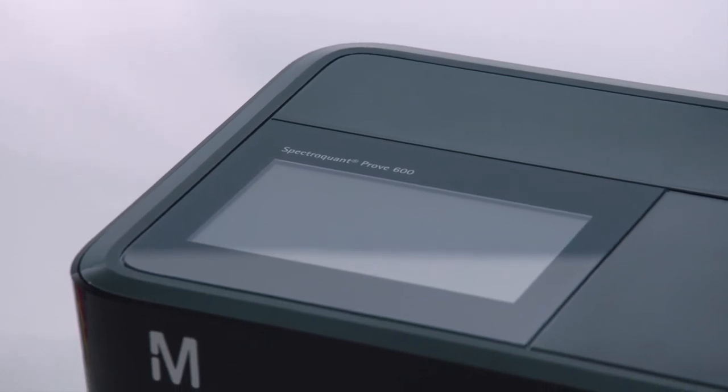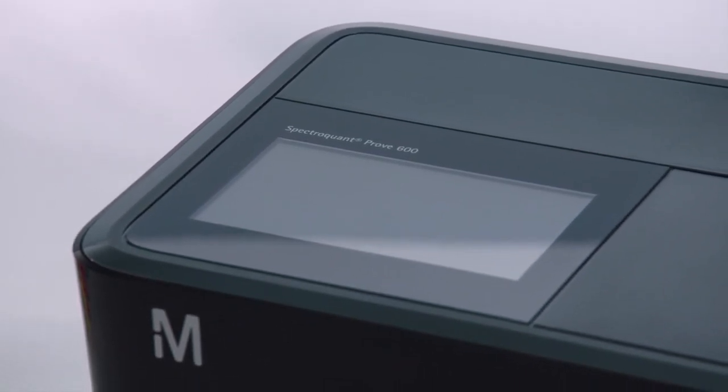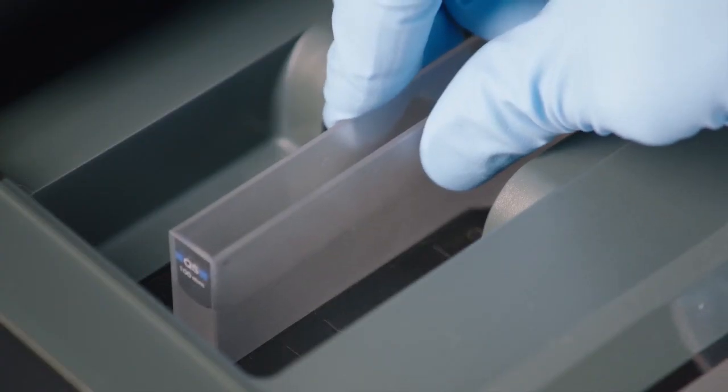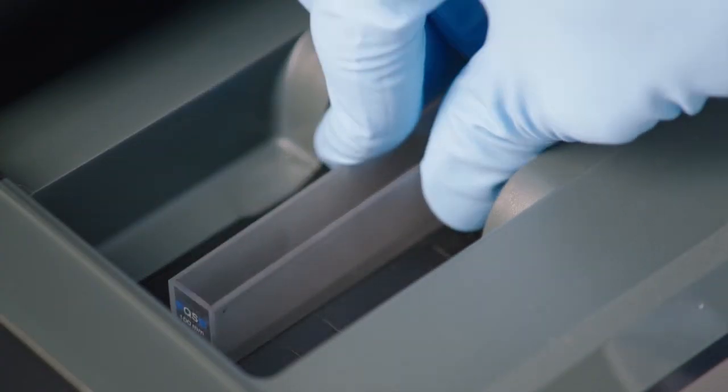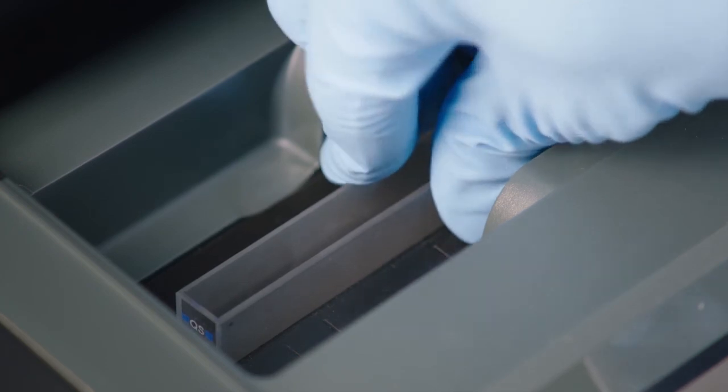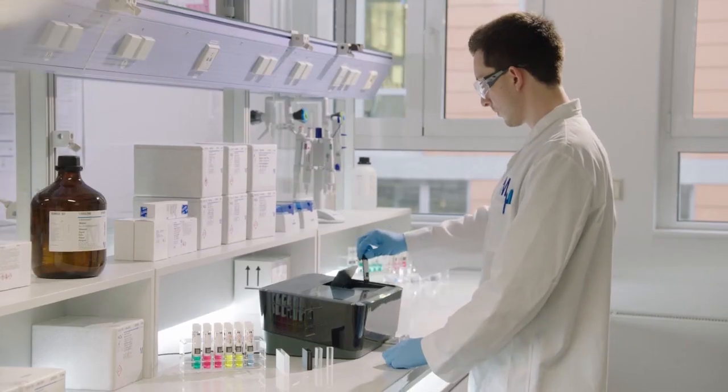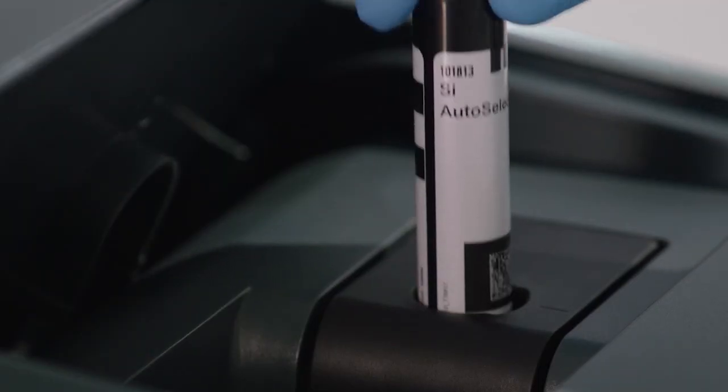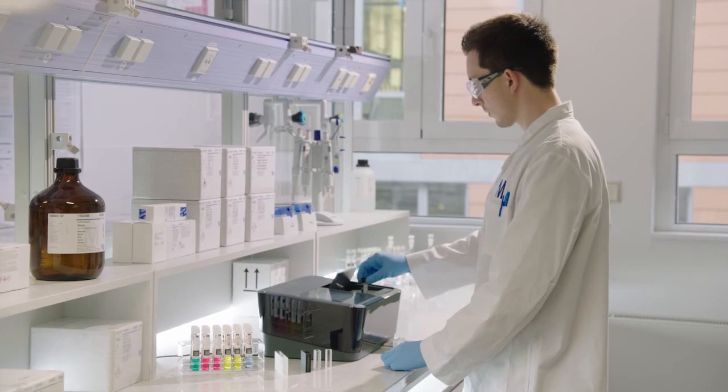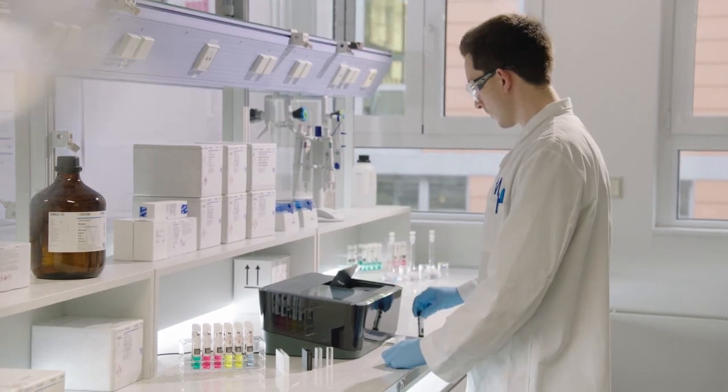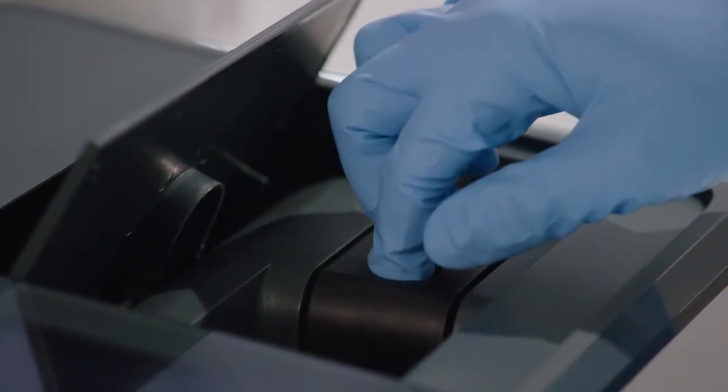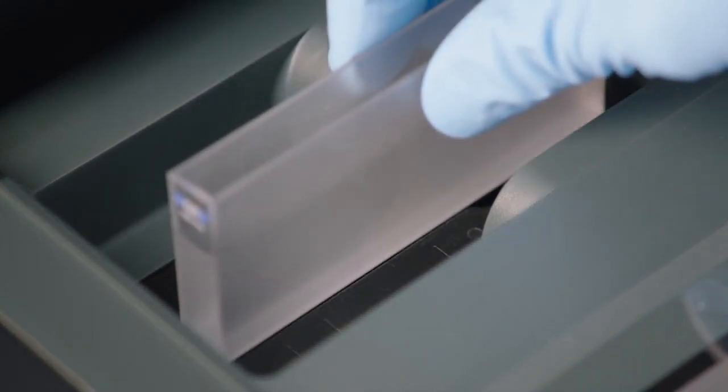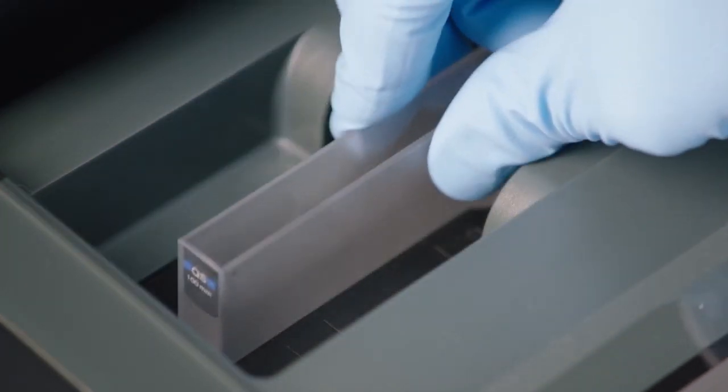Spectroquant Prove 600 also offers a more sensitive measuring option using 100mm cuvettes. Insert the auto selector for method recognition as usual. Then remove the auto selector and the round cell holder. Now you can insert your 100mm cuvette and start your analysis.